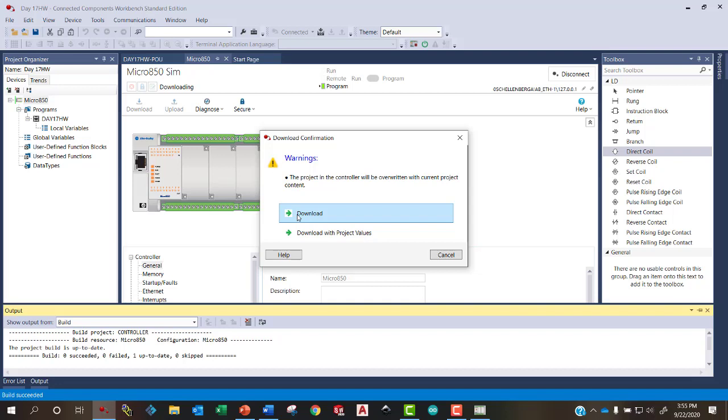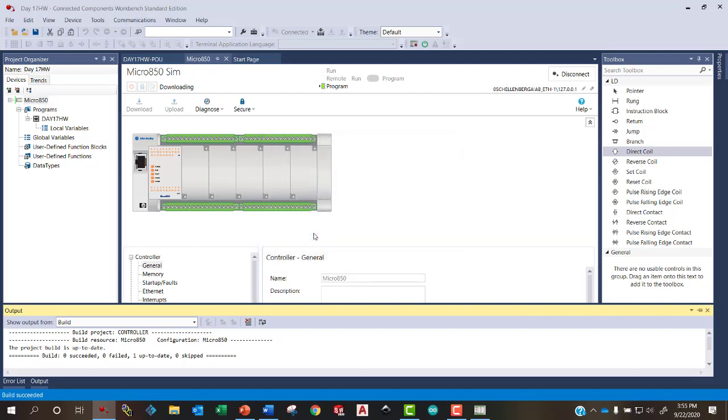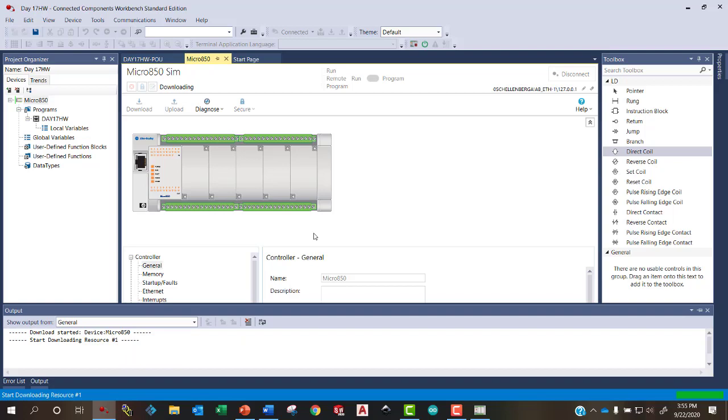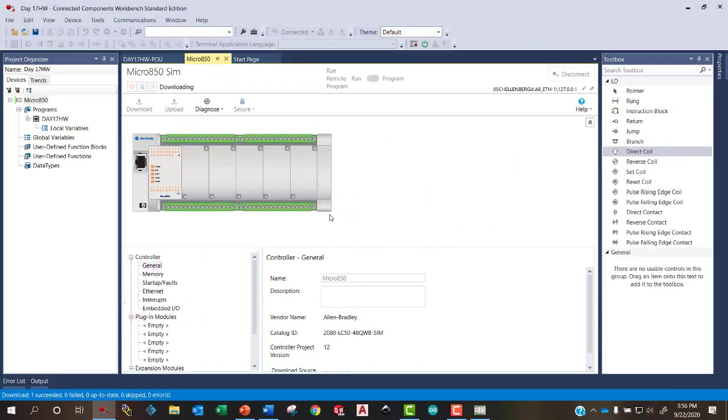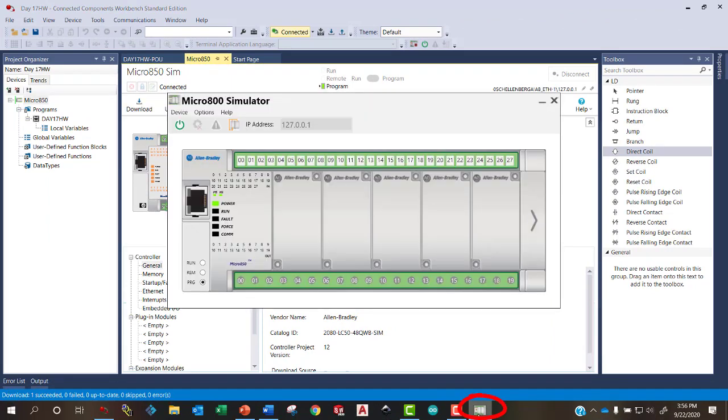And when this window pops up, we can either download the program or download with project values. Downloading with project values is probably the most common. In this particular case, we don't have any project values that we've preset. But this is a good habit to get into to download with project values in case there were any project values that you preset within the program. In the bottom bar in blue, it shows that our download succeeded. So now we can go into our PLC.